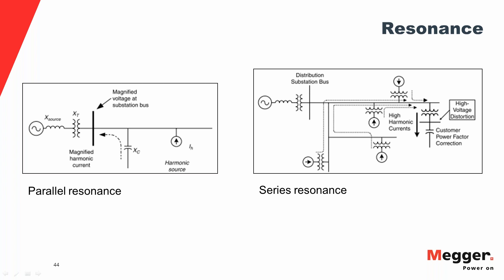Two examples illustrate parallel and series resonance. On the left, a harmonic source has a capacitor bank in parallel with it, plus transformer source impedance — the harmonic source sees a parallel LC resonance circuit. On the right, multiple harmonic sources see a transformer in series with a capacitor bank — a series LC circuit. If the harmonic frequency meets the resonance equation for that series circuit, there will be a high amount of current flow through that branch.